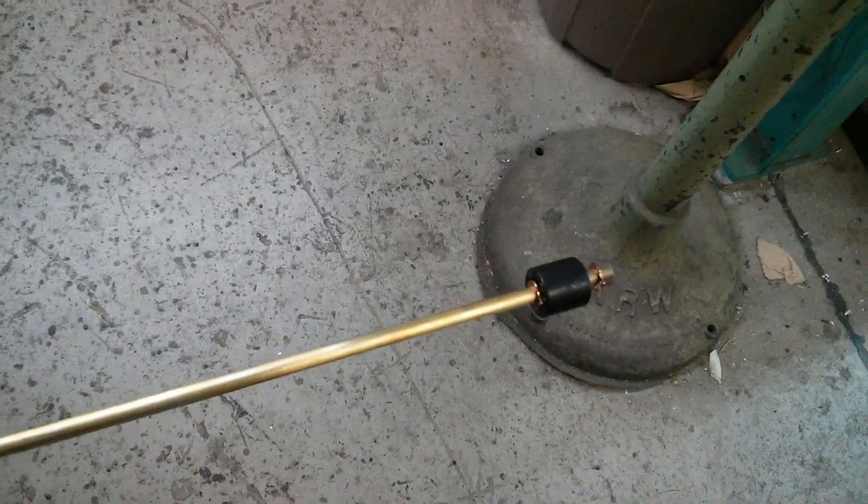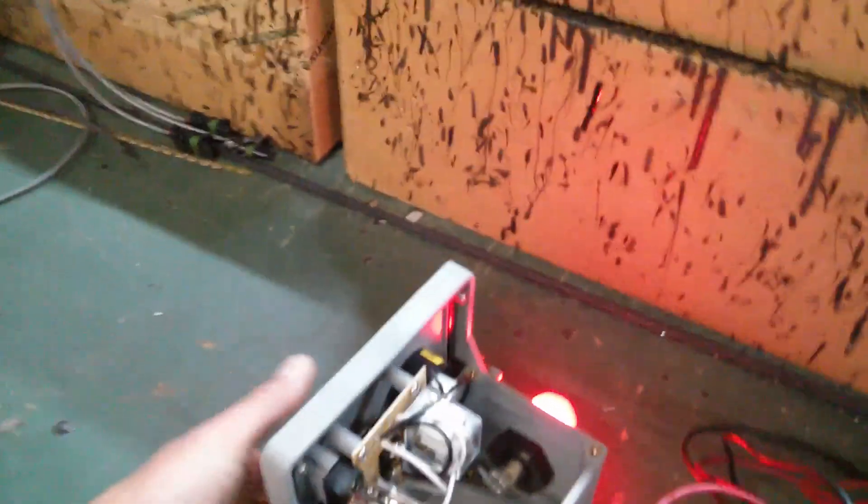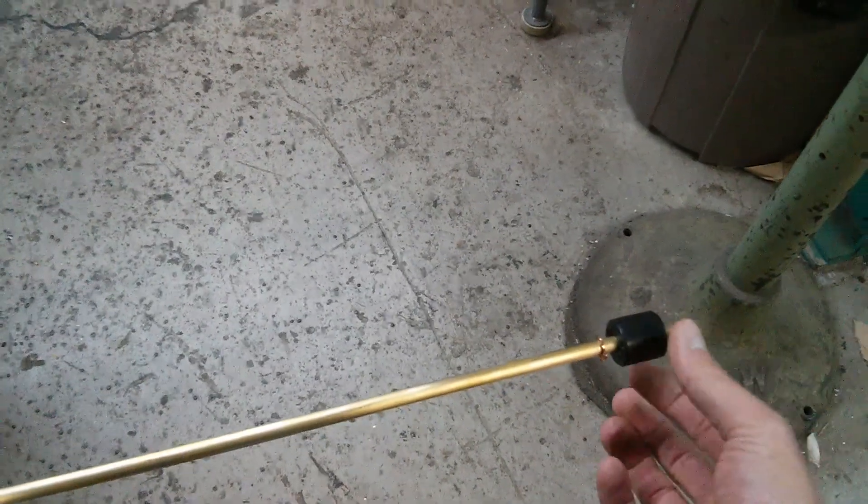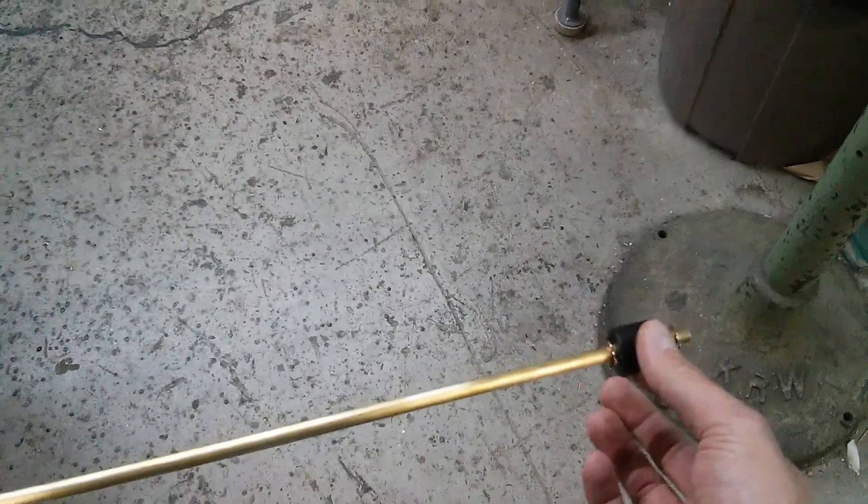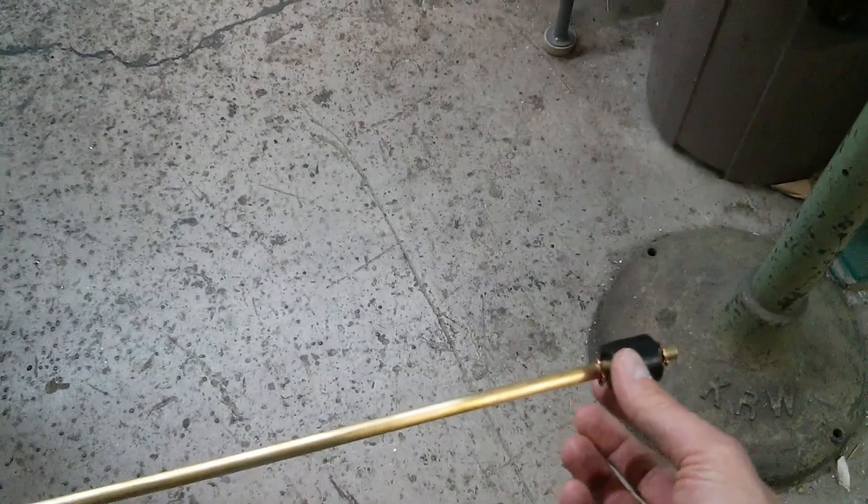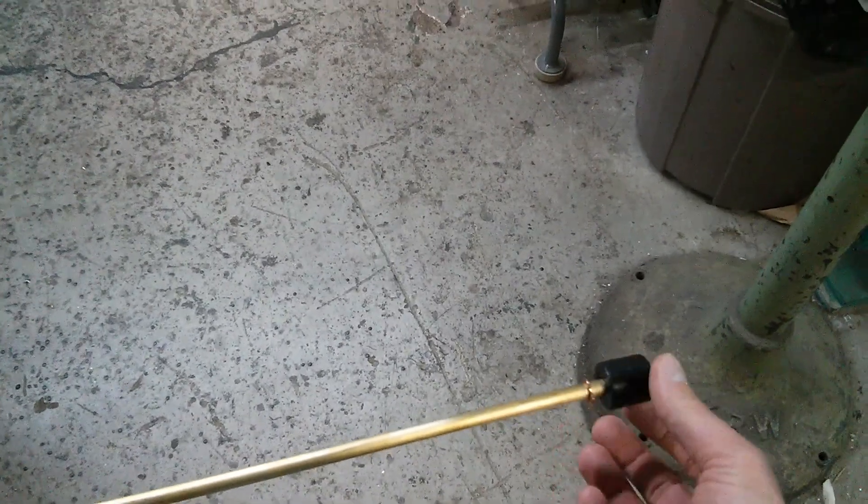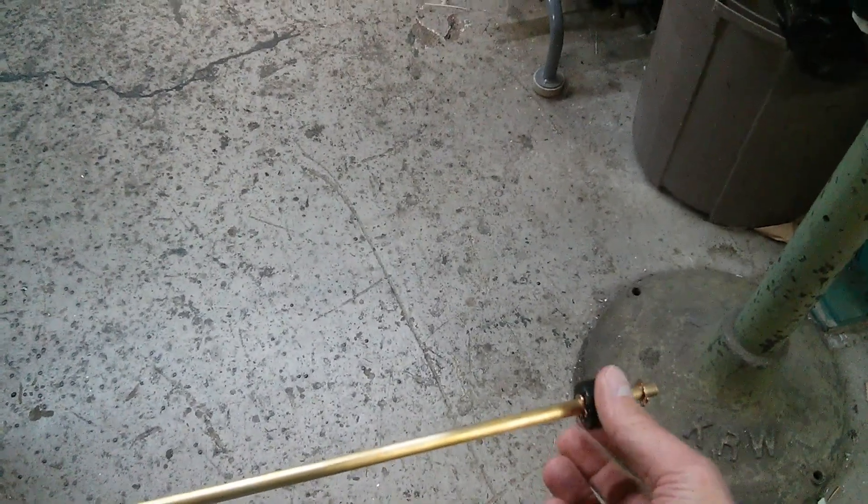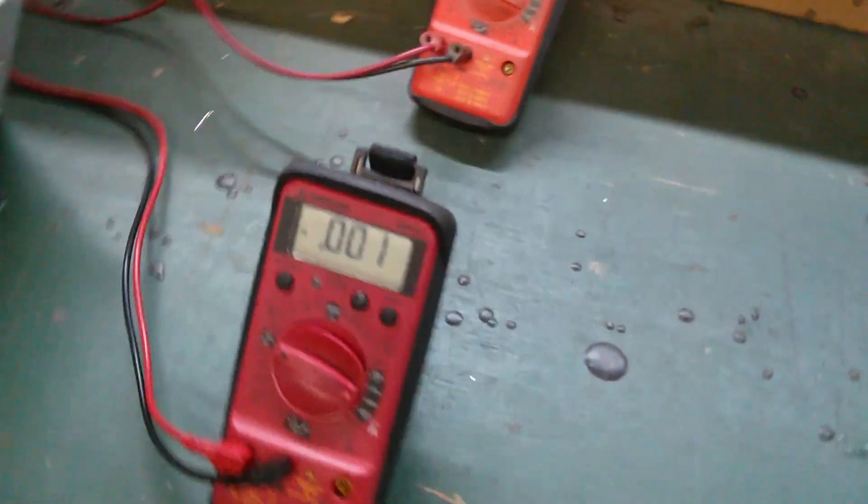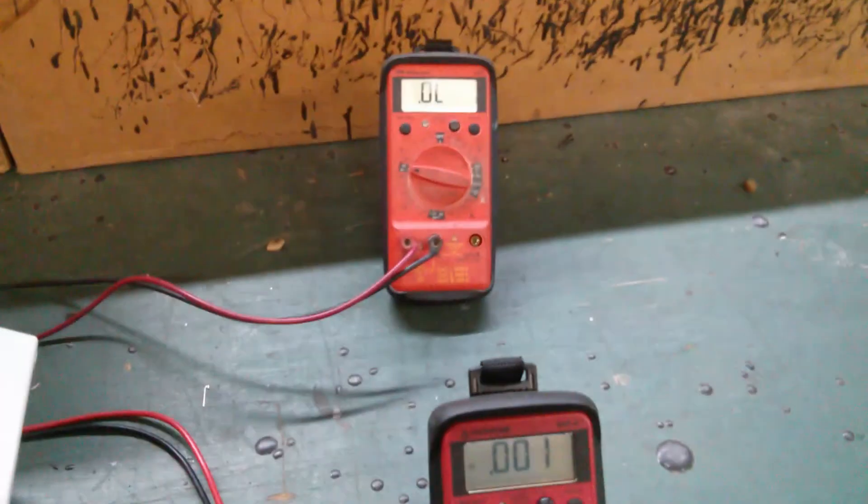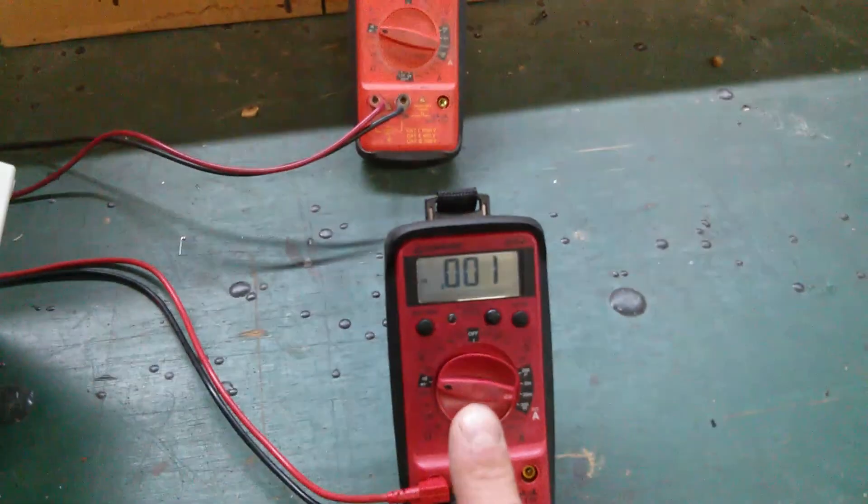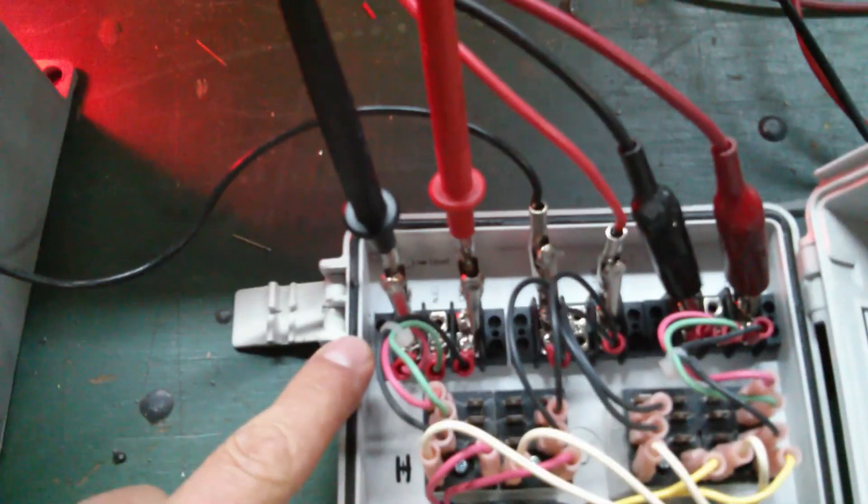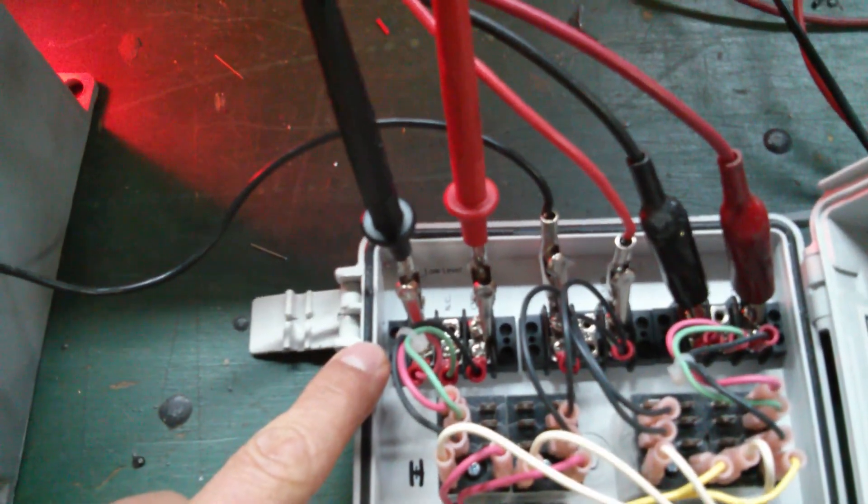We put that up, silence the alarm just for demonstration purposes. Up, down, up, down. So this is activating the low alarm. You can hear the low alarm relay output is activated by moving the float.